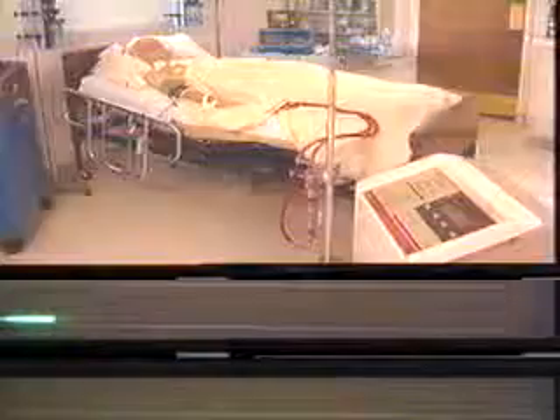To initiate weaning, open the weaning controls compartment and turn the select knob to the right. The weaning indicator will light. The activate light will blink, and the activate message will appear on the LED display. Press and hold the activate button and turn the select knob to set the desired blood flow. When the activate button is released, the console will reduce flow accordingly. If the reduced flow is not tolerated, simply turn the select knob to the off position. The console will automatically resume full flow.